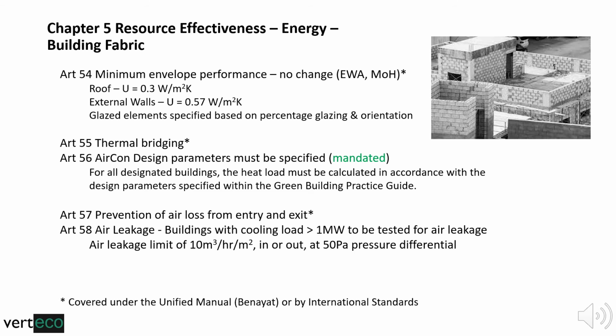Air conditioning parameters must be submitted to the competent authority when applying for permits. This is the only mandated article currently here as far as the GBC is concerned. These represent the load calculation figures normally presented to EWA so EWA can work out the electrical load required for the building. Once you've submitted those figures and EWA has accepted them, this article is deemed passed.